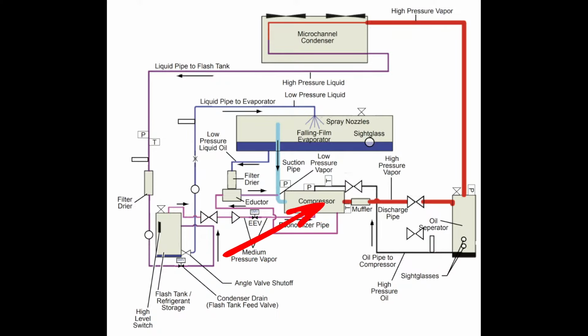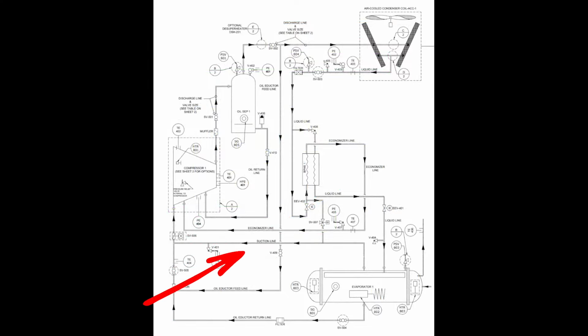So in the Style A technically did have the hot gas line coming off of the compressor initially, but they ended up having to do a field modification where it came off of the discharge line over here because they kept cracking the pipe over here due to vibration, and they were sending too much. The discharge gas leaving this compressor was too oil laden, from my understanding. So they needed to get it over here, for one, it had less vibration, so it didn't break off. But two, we had better oil return because we had less total oil getting sent with that vapor. Okay, so one distinction between the schematics, but in real life, you shouldn't really notice much of a difference.